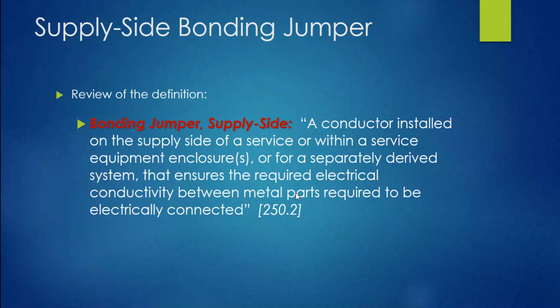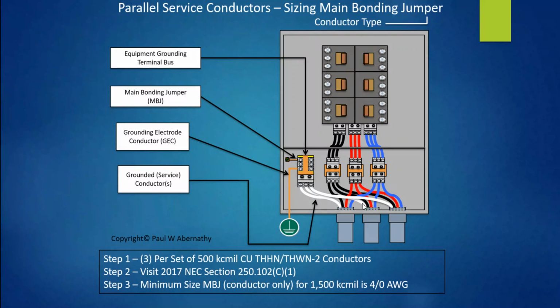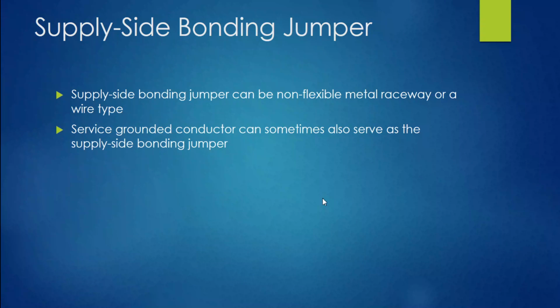And if I showed an example here, it makes the connection here. All of this stuff here is really on the supply side of the service equipment. Here are your service disconnects, okay? So the main bonding jumper here. If these were metal raceways and we had to bond them, we're going to do all that bonding here, and that is considered supply side bonding jumpers. But we're going to see all that here in a minute.